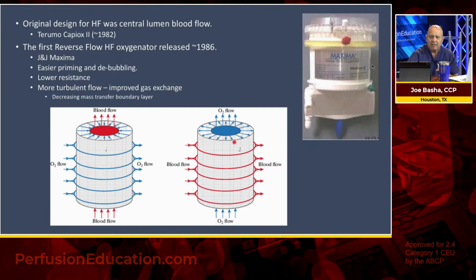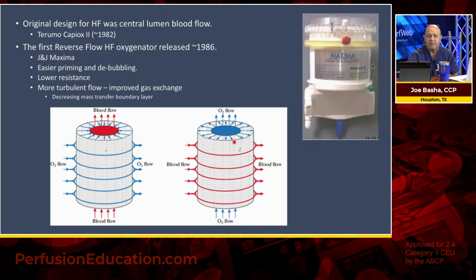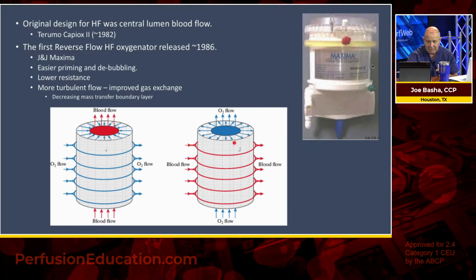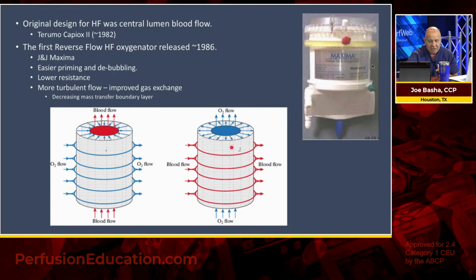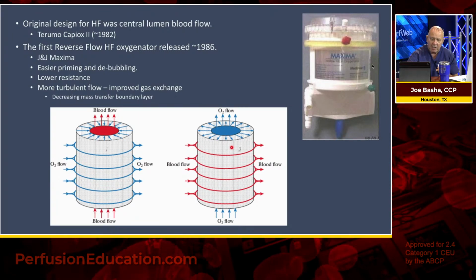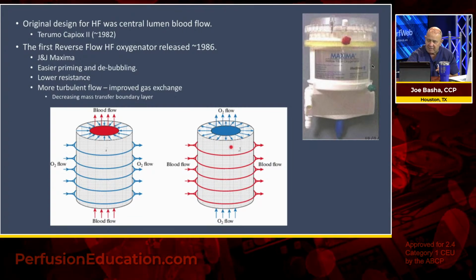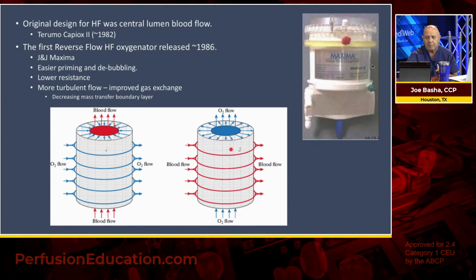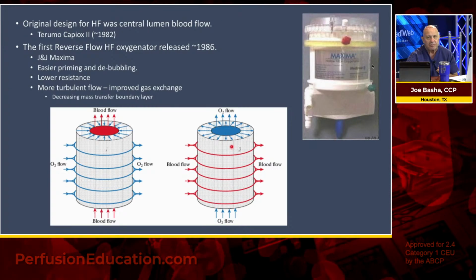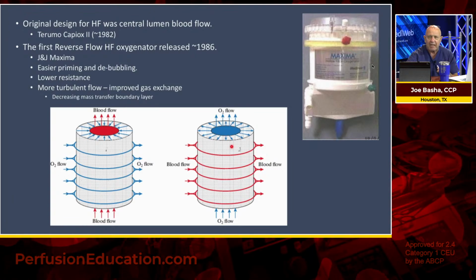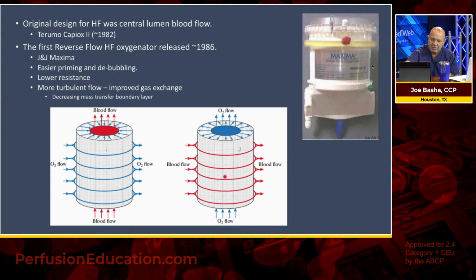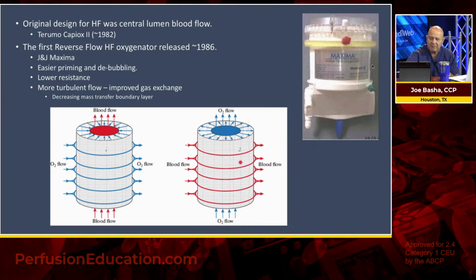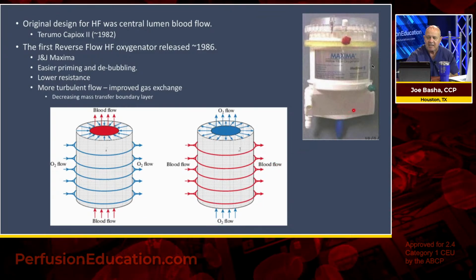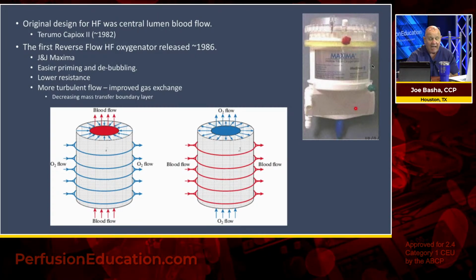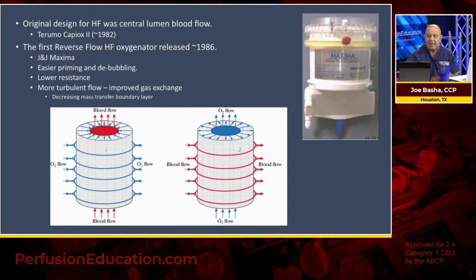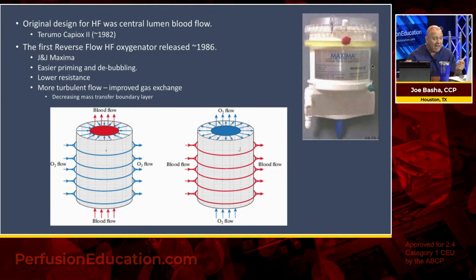On the opposite side, in 1986, plus or minus, Johnson & Johnson created the Maxima Oxygenator, which was the first reverse flow oxygenator that was microporous hollow fiber. It had easier priming than the central lumen or central flow. It was lower resistance for obvious reasons. It's not hard to see why that would be the case. And the more turbulent flow improved gas exchange by decreasing the mass transfer boundary layer, as I talked about. Diffusion boundary, transfer boundary layer all mean the same thing. So you see it represented here, the oxygen or gas flow going through the central lumen and the blood going through the fibers and then out to the patient. And in fact, here is the J&J Maxima Oxygenator. I used many of these. And it's got a very interesting story associated with it, which I hope you will find interesting.